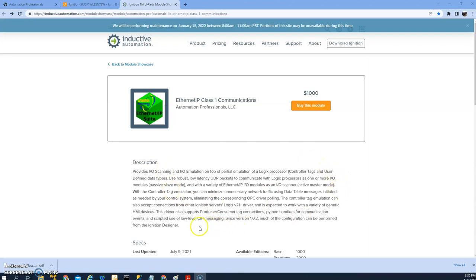It uses UDP instead of TCP for the module. What it does is make Ignition look like a PLC or a virtual PLC to any Allen Bradley class of PLCs like ControlLogix, CompactLogix, MicroLogix, or even PanelView.